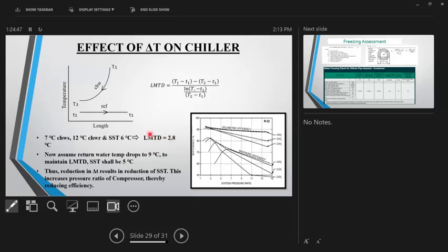So, the heat exchanger performance is not arithmetic actually. It's logarithmic always. So you don't do an average of this. It's actually in a logarithmic way. So the manufacturer will give you a heat exchanger with an LMTD of 2.8. Okay, all done. So you got the chiller selection and you operated the chiller at site.